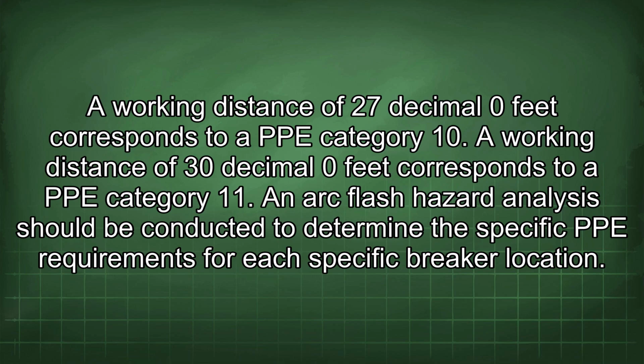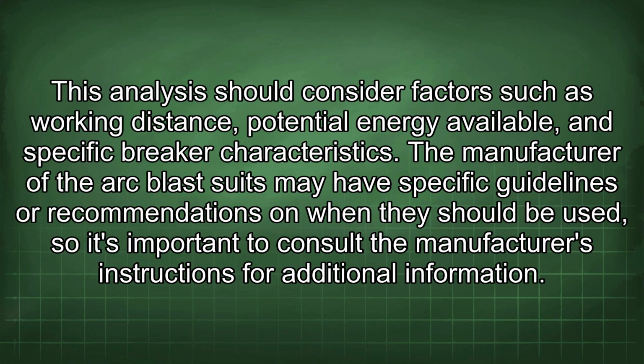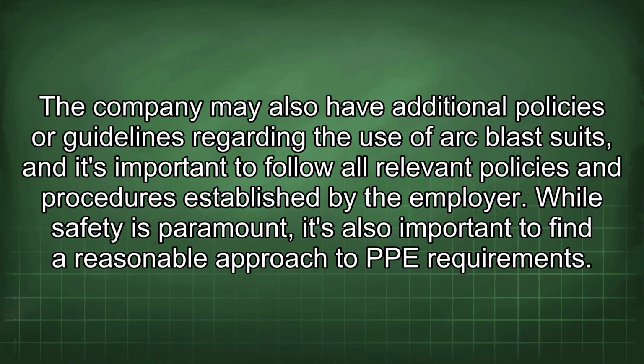An arc flash hazard analysis should be conducted to determine the specific PPE requirements for each specific breaker location. This analysis should consider factors such as working distance, potential energy available, and specific breaker characteristics. The manufacturer of the arc blast suits may have specific guidelines or recommendations on when they should be used, so it's important to consult the manufacturer's instructions for additional information. The company may also have additional policies or guidelines regarding the use of arc blast suits, and it's important to follow all relevant policies and procedures established by the employer.